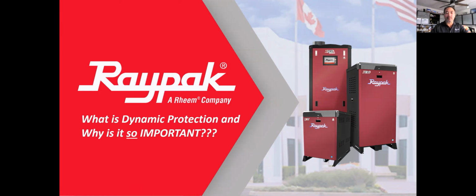I've been with Raypak for over 23 years now, and we've seen the evolution of boilers in the industry. Actually, it was cast iron, high mass, steel tube, fire tube, so water-backed fire tube, etc. We didn't have a lot of problems with those units. They weren't that efficient. A lot of them lasted for many, many years. Of course, we'd have some of the basic issues associated with them. But when we started seeing more and more stainless steel, the condensing style, we started seeing some very distinct issues. So that's what I want to talk to you about.